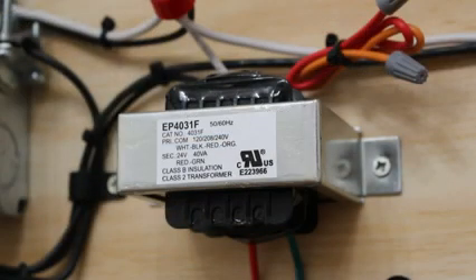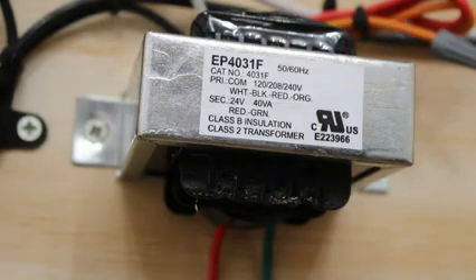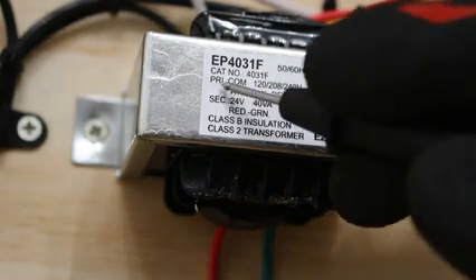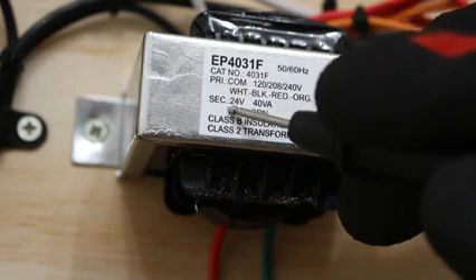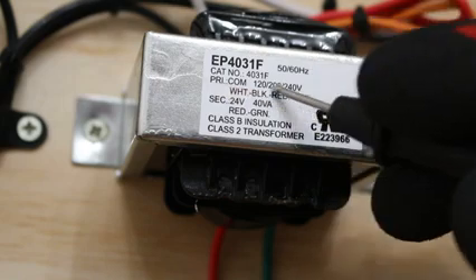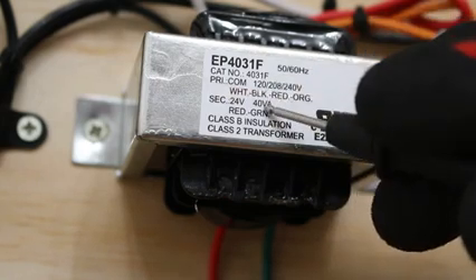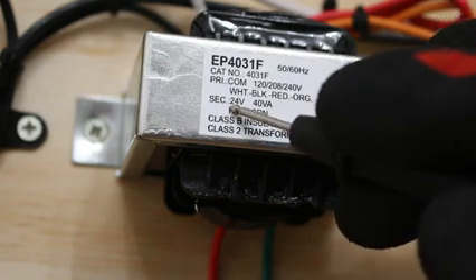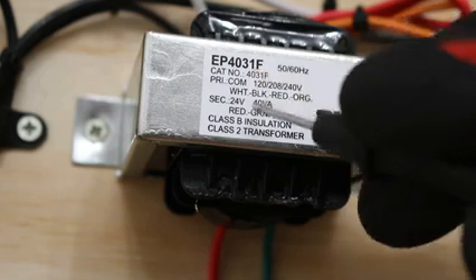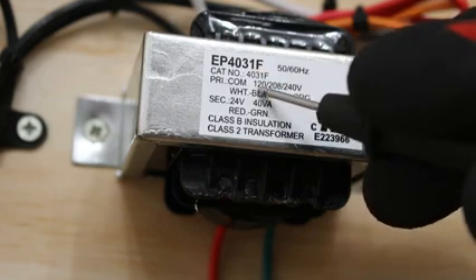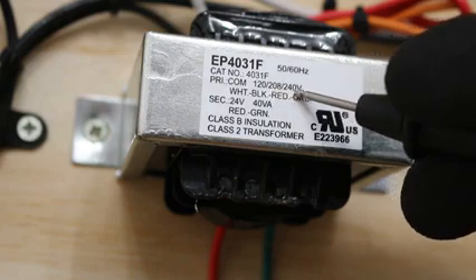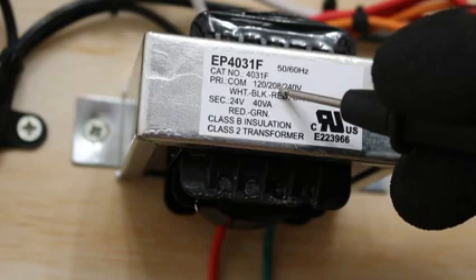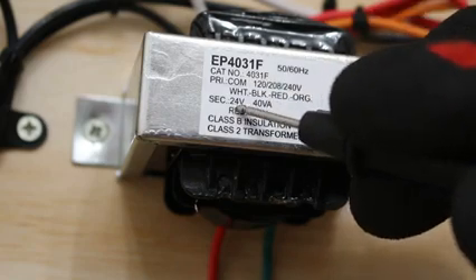Before we can begin troubleshooting, it's important to understand what a step-down transformer is and how it actually works. Essentially, a step-down transformer is an electrical component that steps down the voltage. Your transformer consists of two coils, a primary coil and a secondary coil. Your primary coil is always going to have the higher rated voltage, and then we step down the voltage to our secondary coil, which is going to be lower. In this case, this transformer can either be 120, 208, or 240 volts as your incoming power at the primary coil, and then it steps it down to 24 volts.